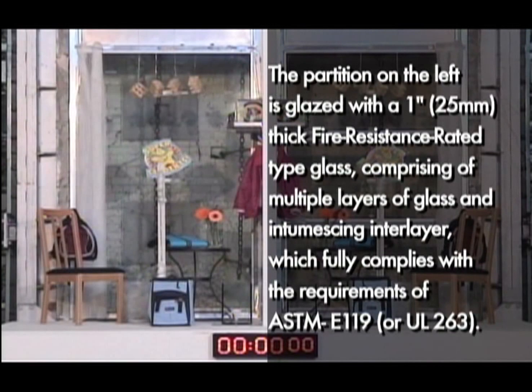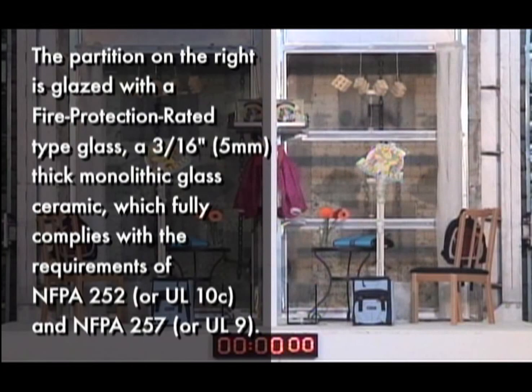The partition on the left is glazed with a 1-inch thick fire-resistant rated type glass comprising multiple layers of glass and intumescing interlayer, which fully complies with the requirements of ASTM E119. The partition on the right is glazed with a fire-protection rated type glass, a 3/16-inch thick monolithic glass ceramic, which fully complies with the requirements of NFPA 252 and NFPA 257.